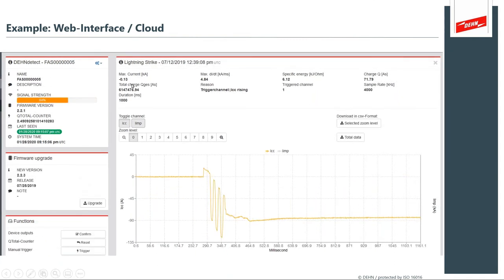Here's a data capture of what's considered a fairly mild event — more like an ICC event. It's not an incredibly high strike, but it persisted for enough milliseconds to deliver quite a bit of charge. And again, you see the accumulated charge over time.